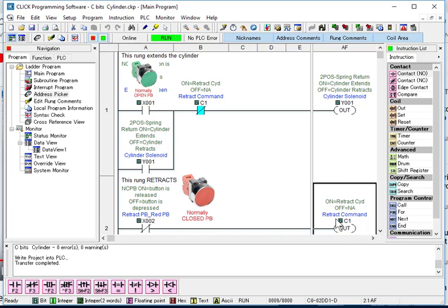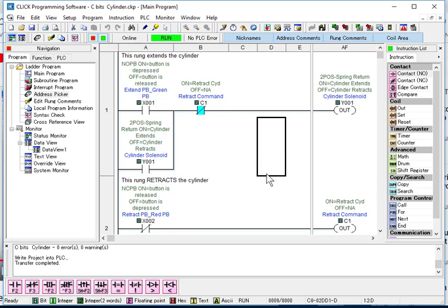And output modules are a certain cost, and wiring them to do nothing makes no sense, so that's the purpose of C coils. So they're really just like Y1 is sealing in that, hey, somebody has hit X1. We can use C1, C2, etc. for whatever that is. So internal coils, I just use for logic. And remember, we can use them over here. So that could be a C, this could be a C, whatever we want.